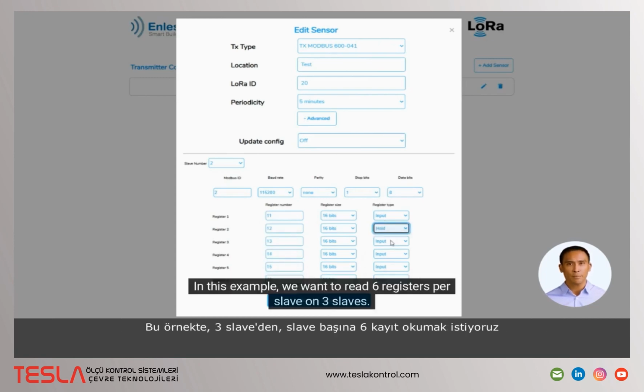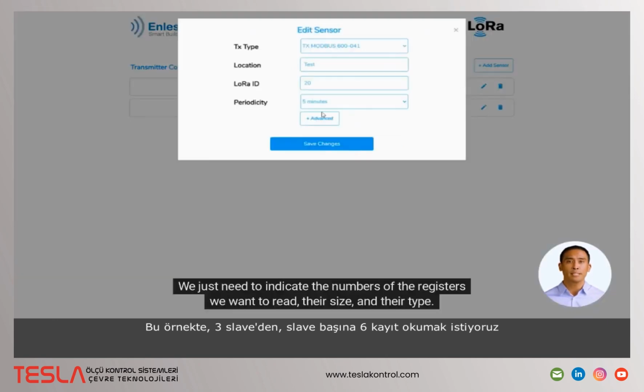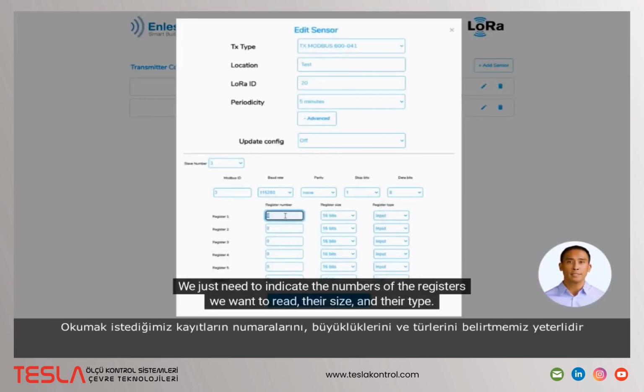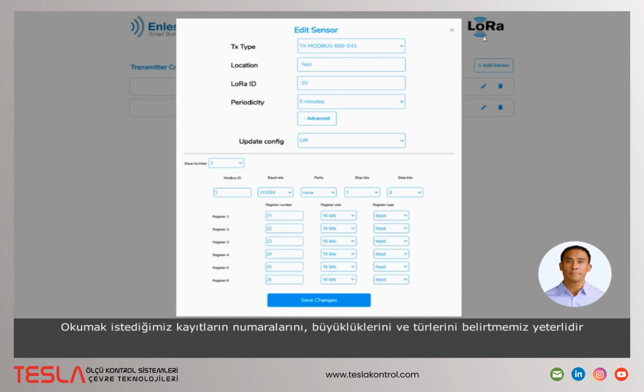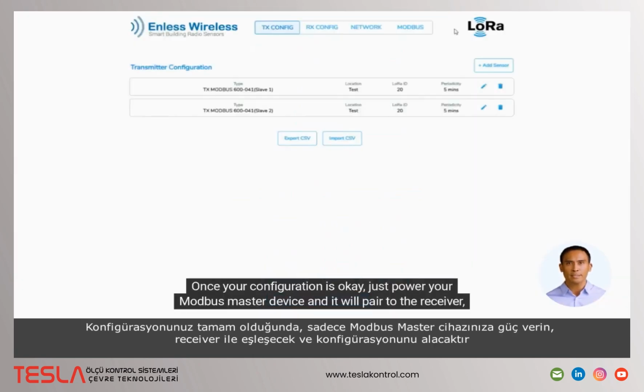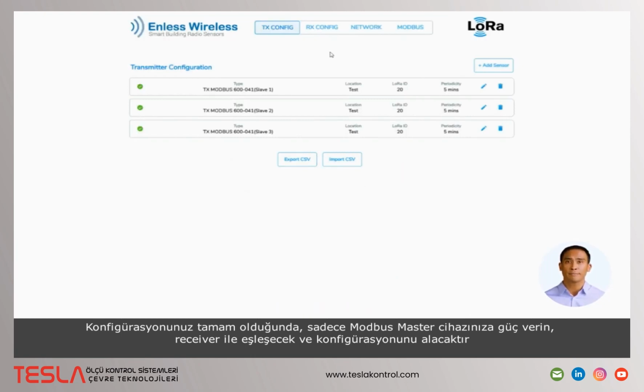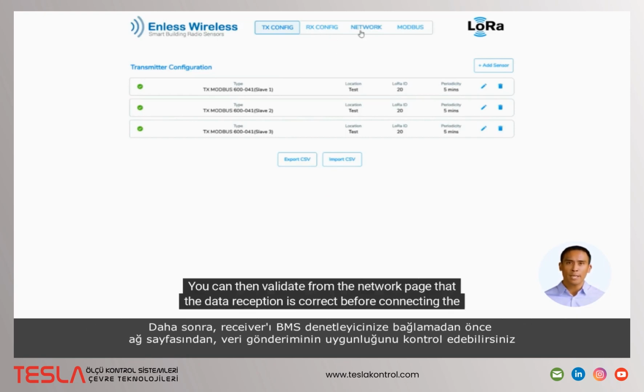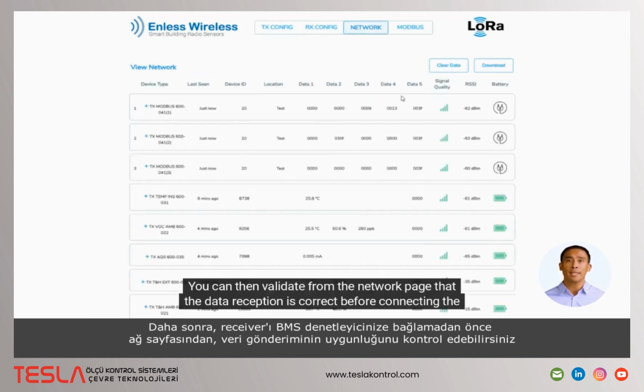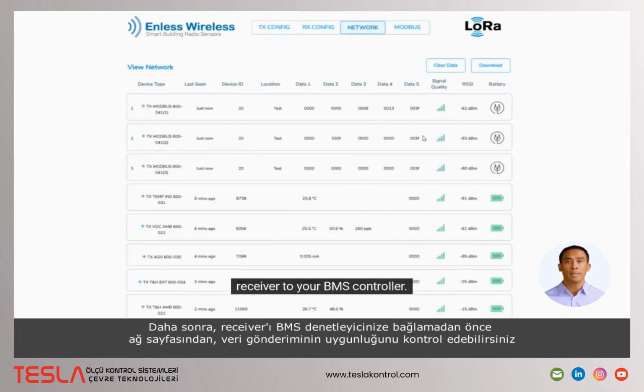In this example, we want to read 6 registers per slave on 3 slaves. We just need to indicate the numbers of the registers we want to read, their size, and their type. Once your configuration is okay, just power your Modbus Master device, and it will pair to the receiver and get its configuration. You can then validate from the network page that the data reception is correct before connecting the receiver to your BMS controller.